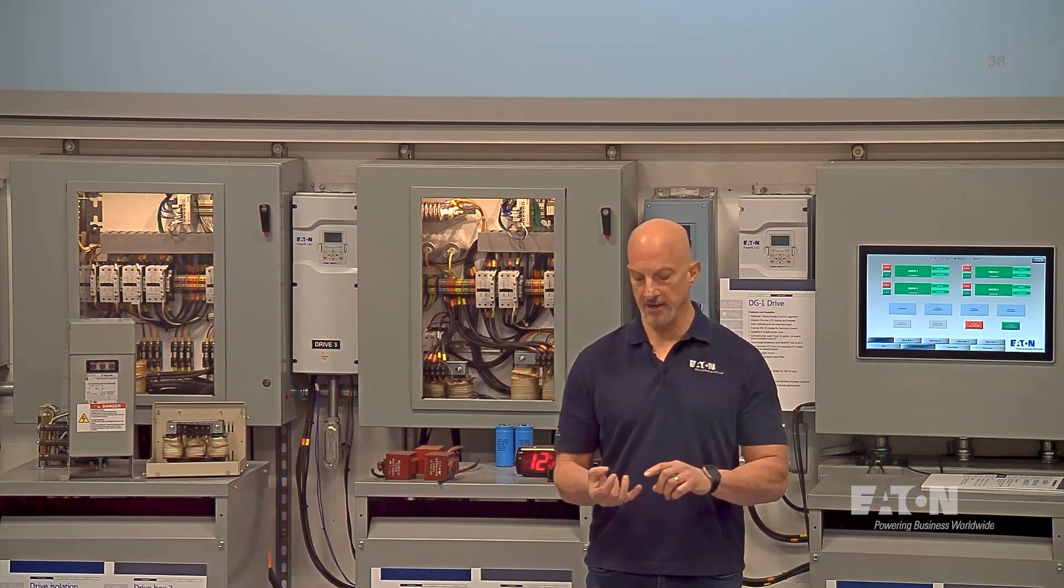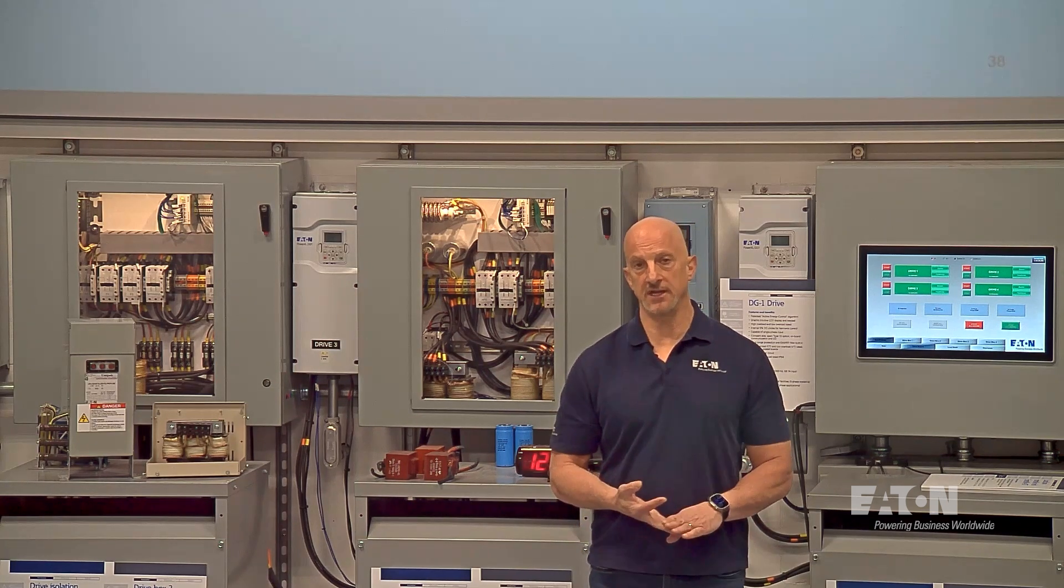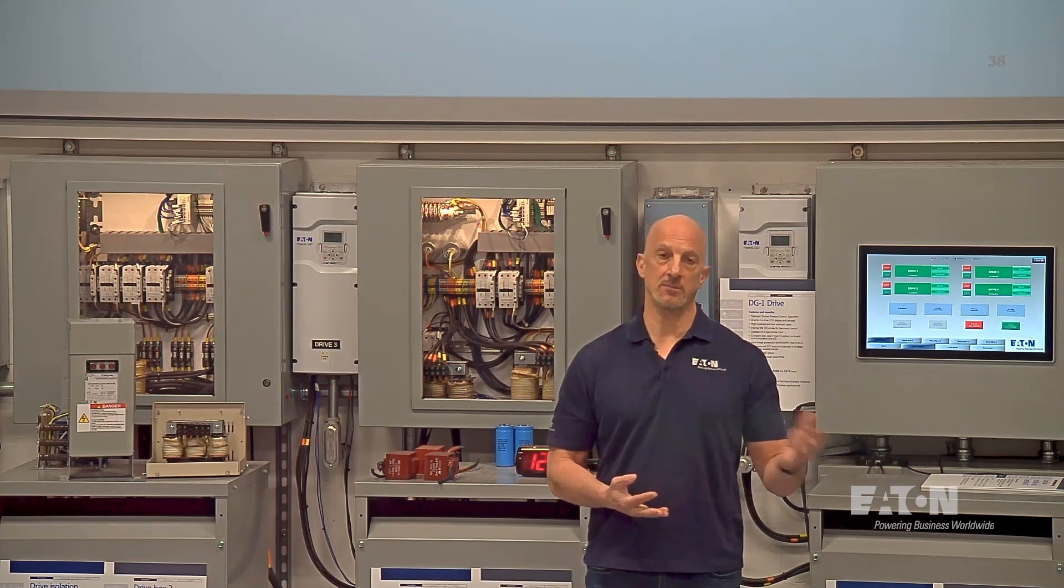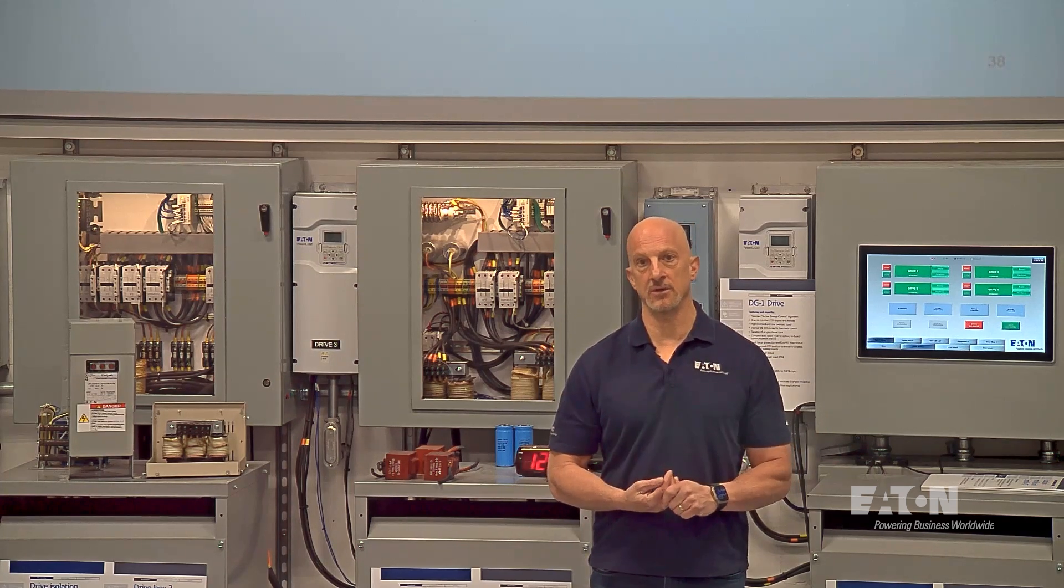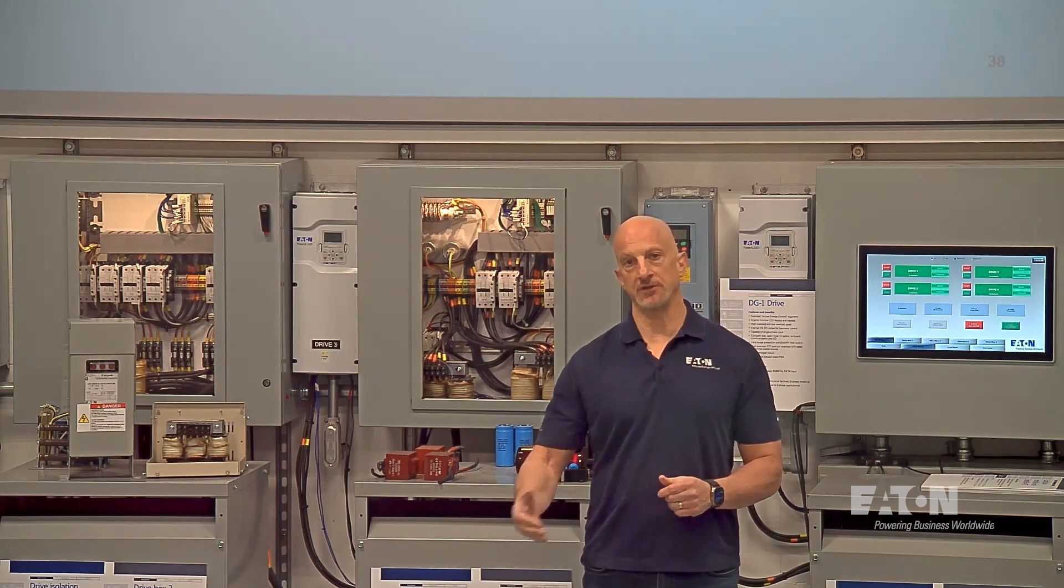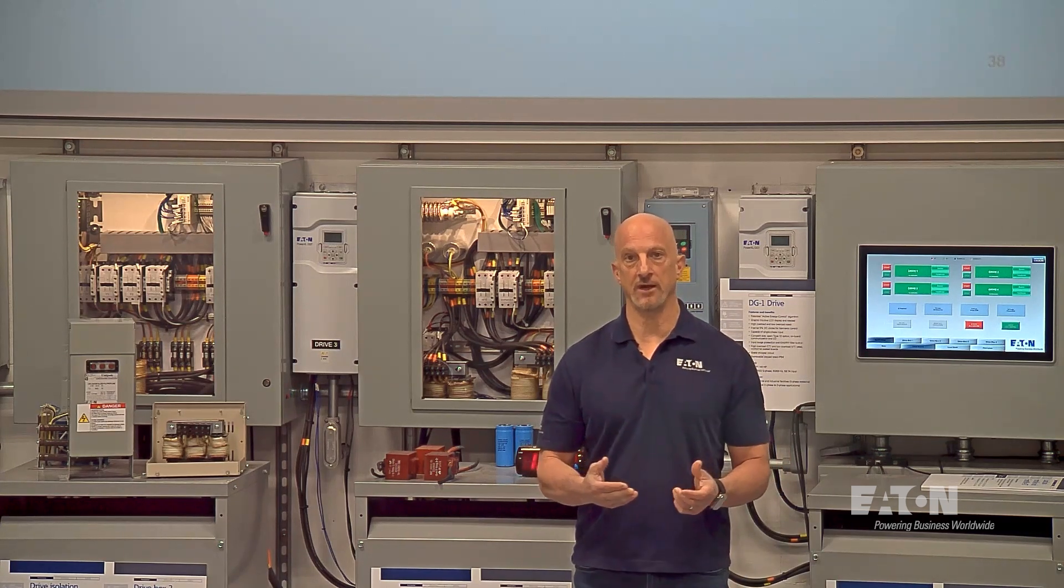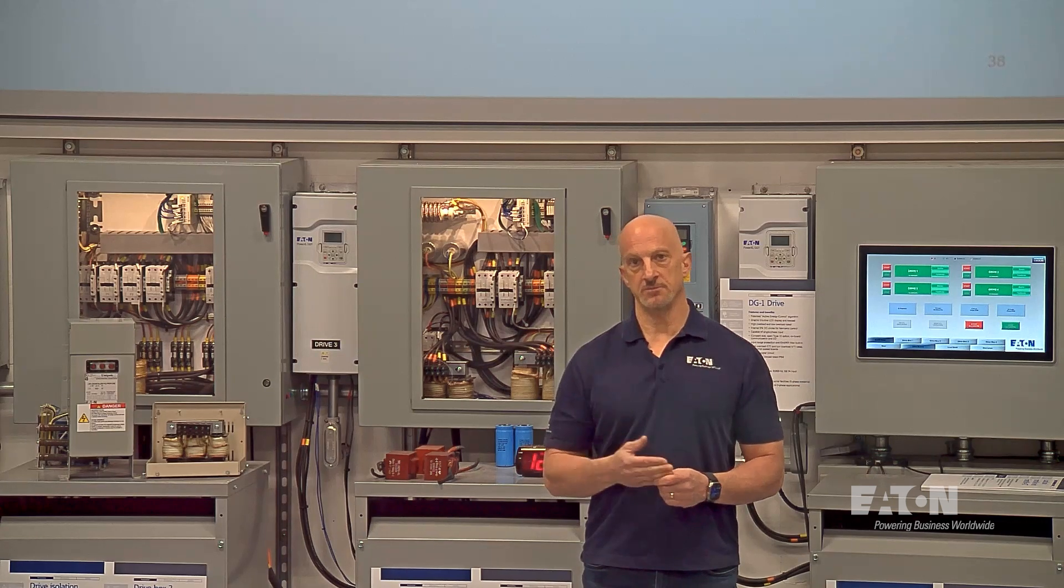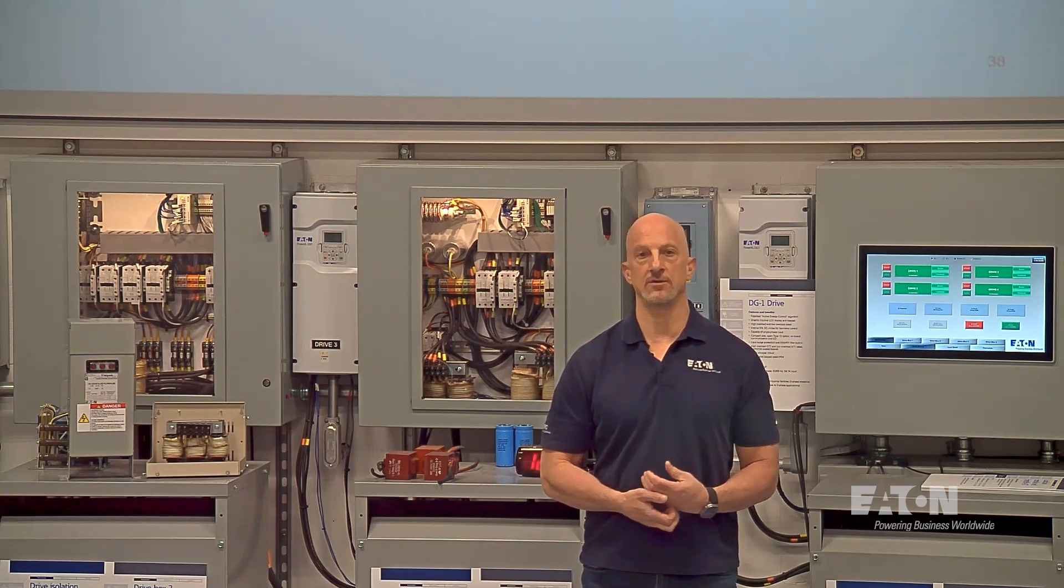If we have three phase loads like VFDs, we're going to have certain harmonics, and we talk about characteristic harmonics in some of the other videos like NP plus or minus one for drives, six pulse drives. So six plus or minus one—fifth and seventh, two times that—eleventh and thirteenth.